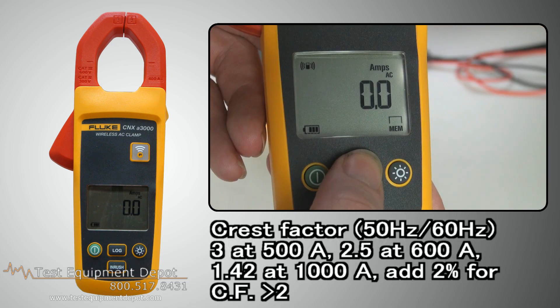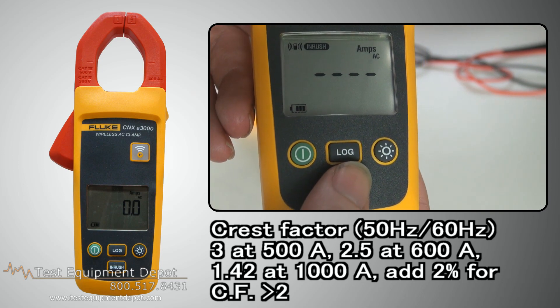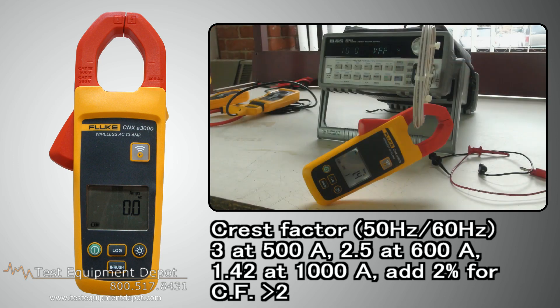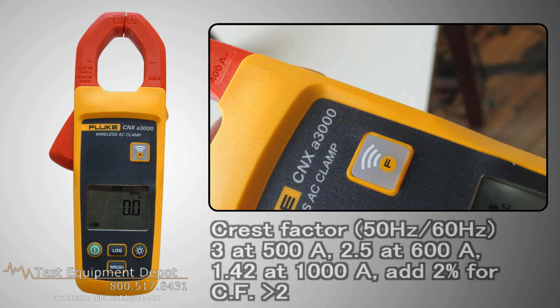It has a crest factor at 50 hertz and 60 hertz of 3 at 500 amps, 2.5 at 600 amps, 1.42 at 1000 A, and you add two percent for crest factors greater than two.